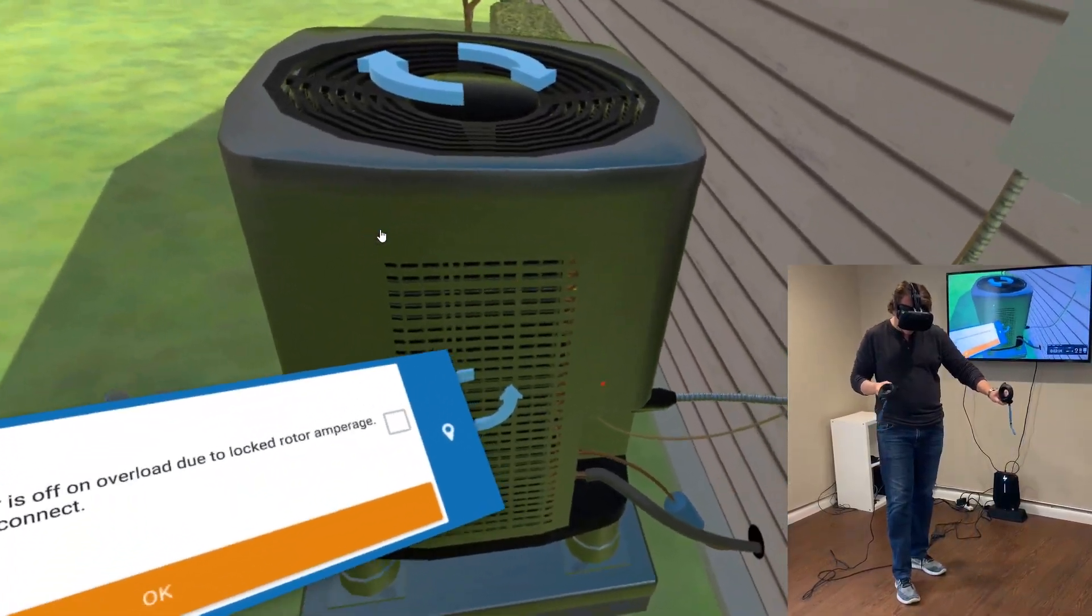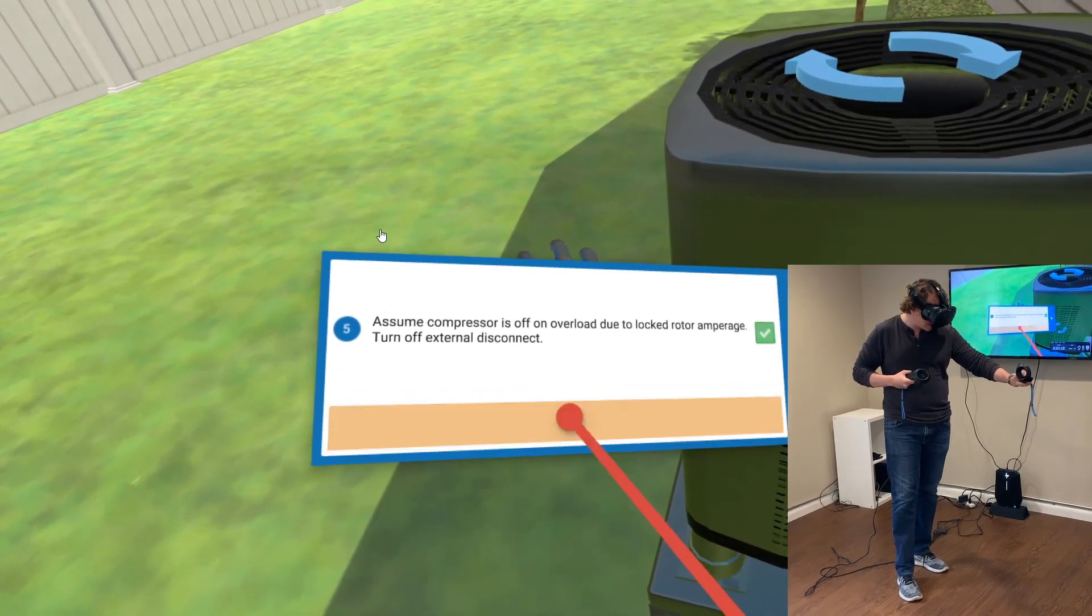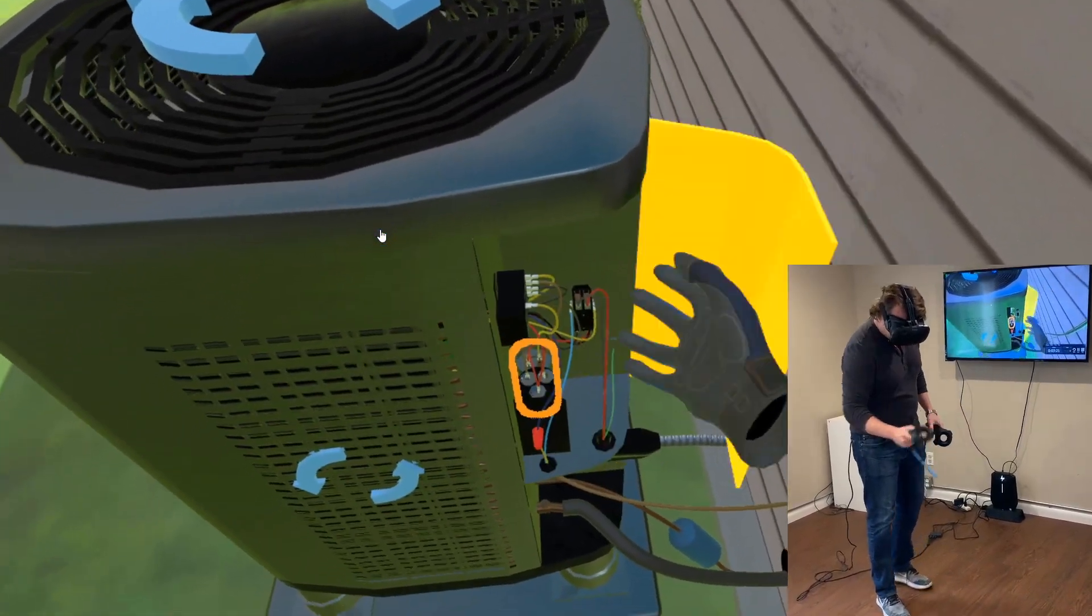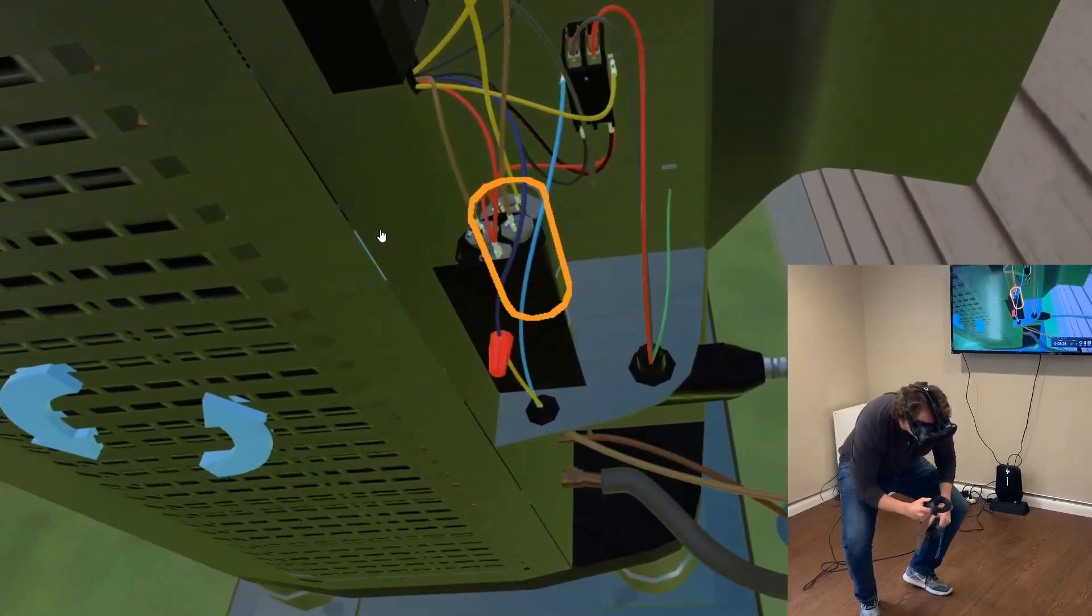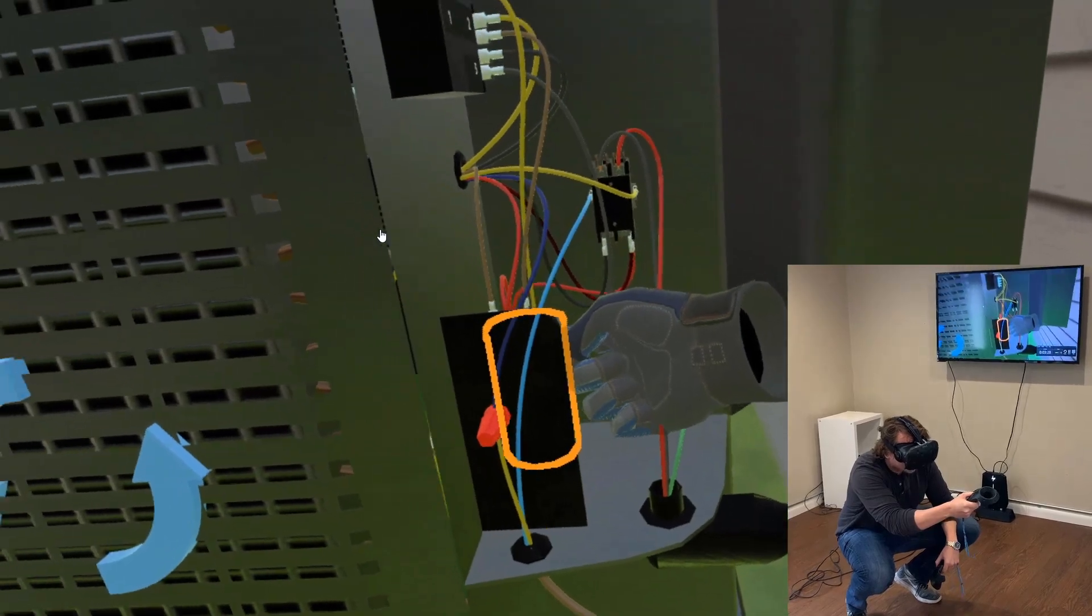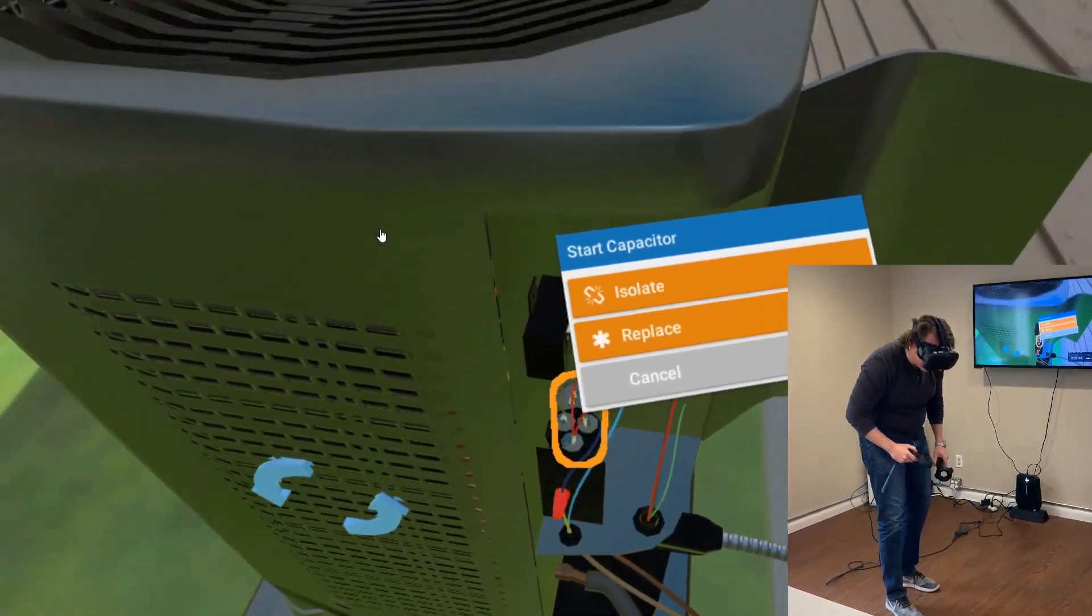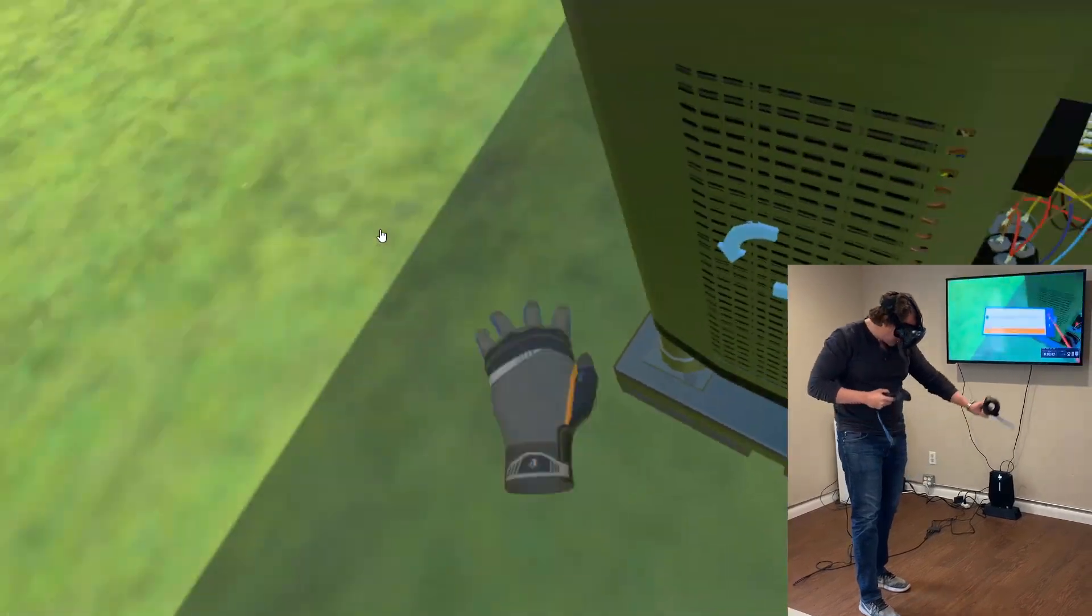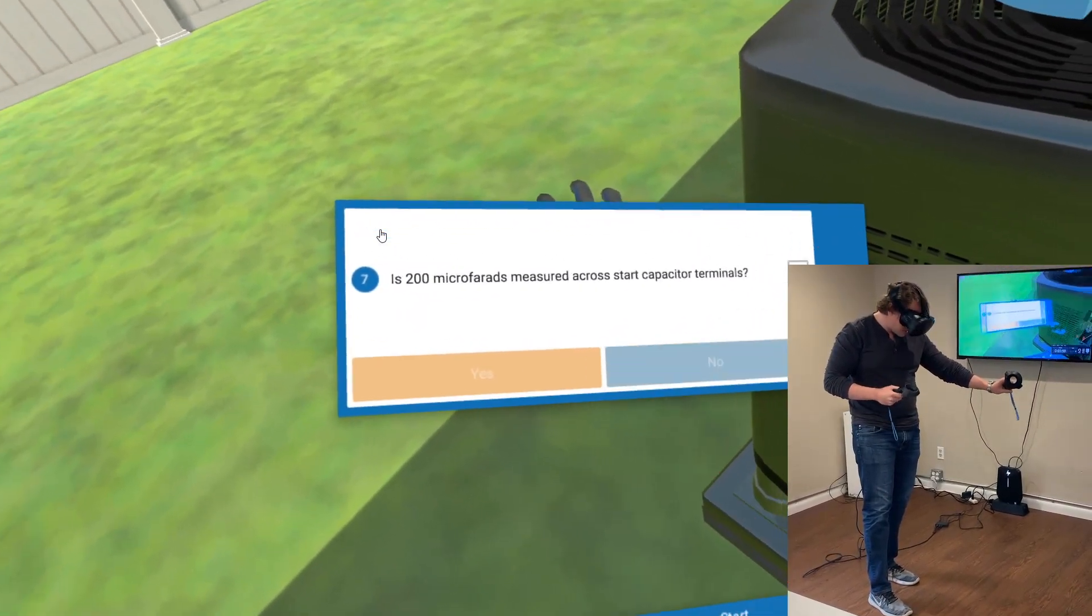Now we're going to dive into some investigation of this outdoor unit. Disconnect the yellow wire from the start capacitor. Discharging of the capacitor has automatically been done for you - it's always going to be a bit of a full body experience here in VR. I'm going to isolate this start capacitor, which is 200 microfarads.